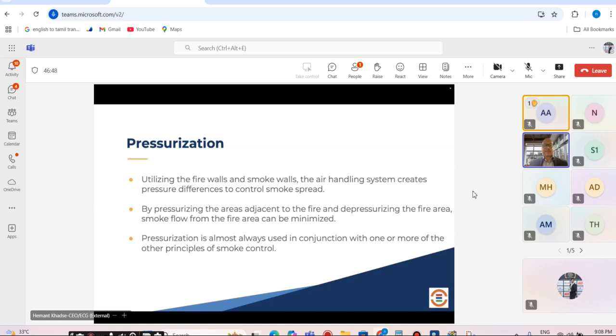Also, another scenario: when you build a cause and effect diagram for a pressurization system, what if there is a false alarm? How is it going to lead to the pressurization? Your detection system is not so reliable, or maybe it will give you a delayed detection. Instead of giving the fire zone floor detection first, it is going to give you detection on the upper floor first, which will lead to the activation of that particular floor's pressurization. It might lead to different outcomes, because you will have different strategies to activate.